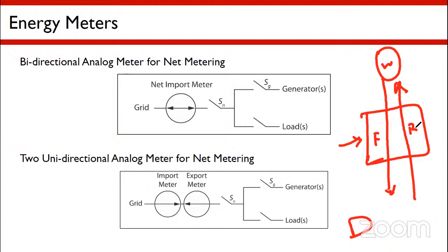So whenever current flow is detected, the incremental counter works: 1, plus 1, plus 1. It keeps on increasing: 3, 4, like that. So the problem is, if you use a normal meter for a solar application, the meter will record the export as import. That is why we go for a bidirectional meter.